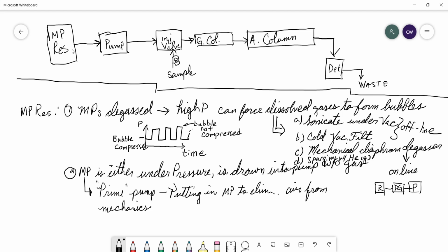So what we actually do with these mobile phase reservoirs, instead of pumping them into the side, like you might think, what we actually do is we bring them around and we pull it into the pump, push it into the pump from the bottom, and then the pump usually outlets out the top. Okay? As opposed to out its side. That way, any air that's in the pump, okay, and we have a little valve here, any air that's in the pump can be forced out, and then the lines are free of any gas.